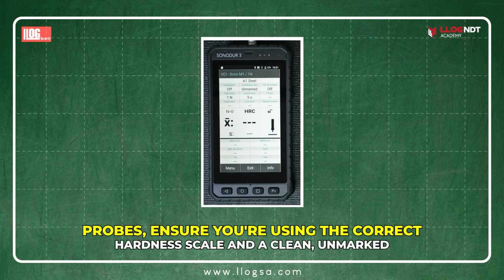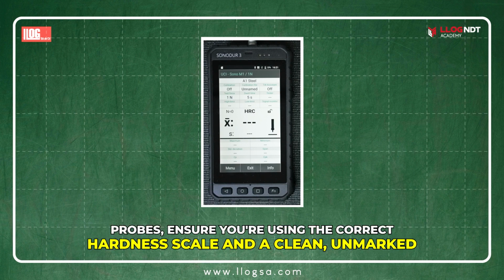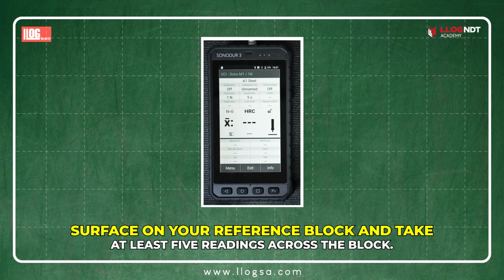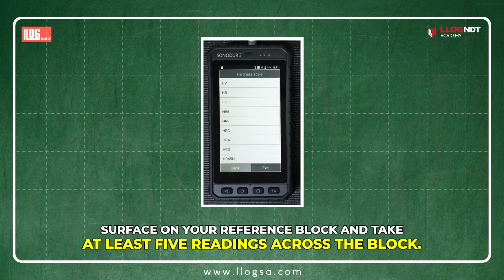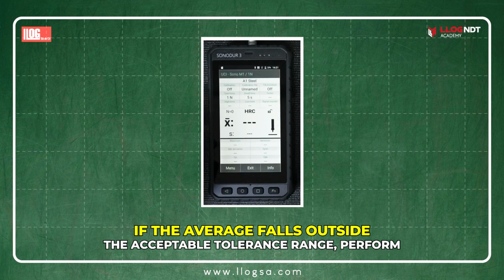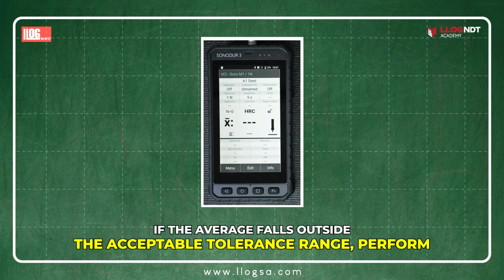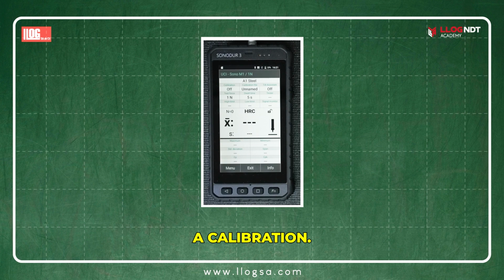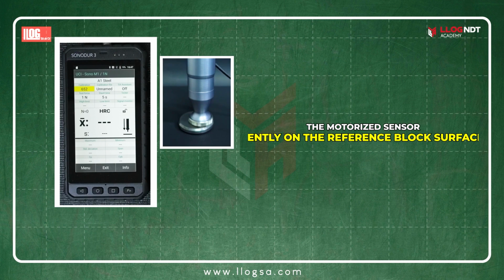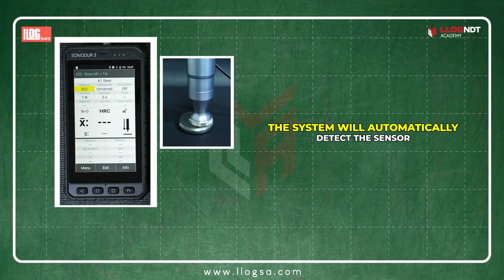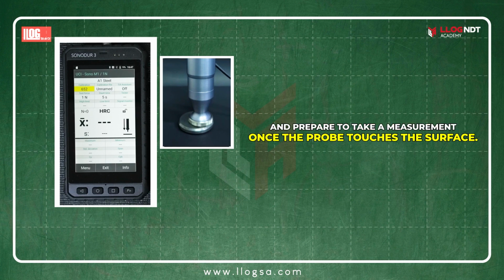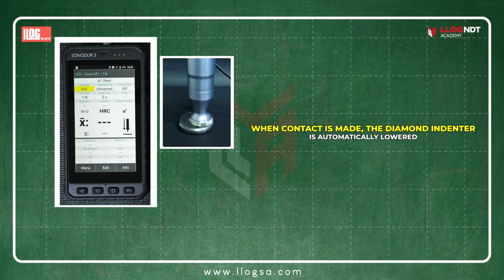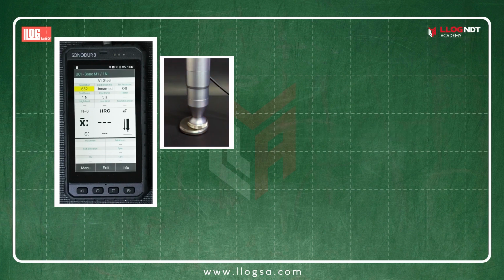As with manual probes, ensure you're using the correct hardness scale and a clean, unmarked surface on your reference block, and take at least 5 readings across the block. If the average falls outside the acceptable tolerance range, perform a calibration. Place the motorized sensor gently on the reference block's surface. The system will automatically detect the sensor and prepare to take a measurement once the probe touches the surface. When contact is made, the diamond indenter is automatically lowered, and the dwell time countdown begins.